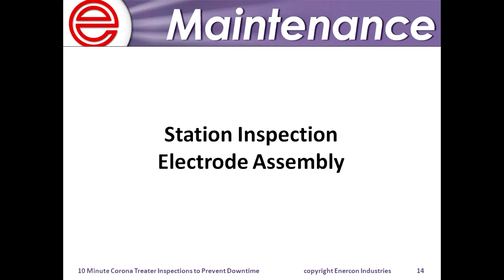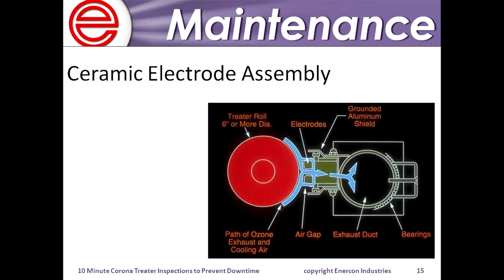Now, after everything's locked out, we'll talk about inspecting the electrode assembly. The first thing we want to overview is the design in which our electrode assembly functions — this shows how the exhaust airflow is concentrated in our efficient design to effectively cool the electrodes and remove the ozone.